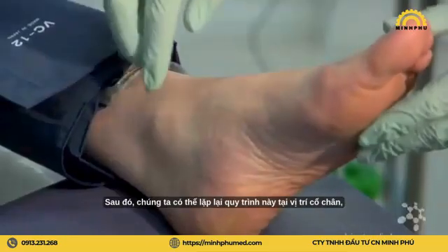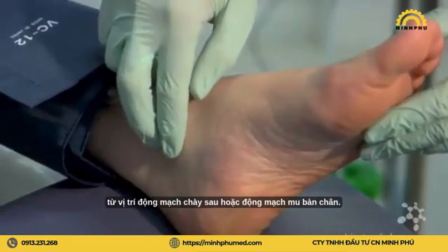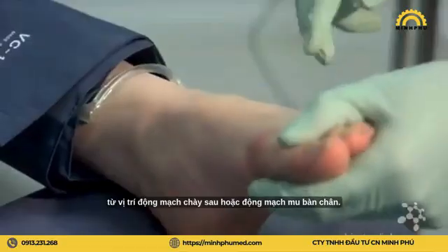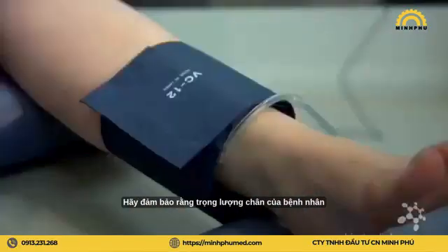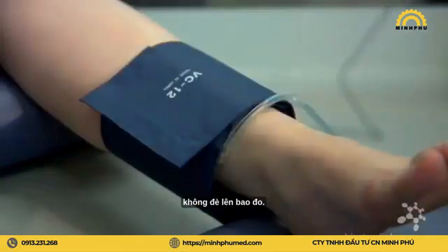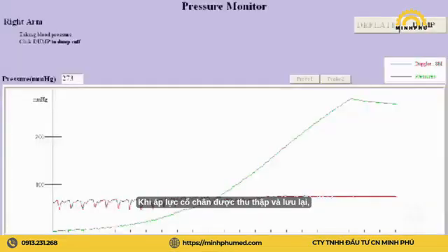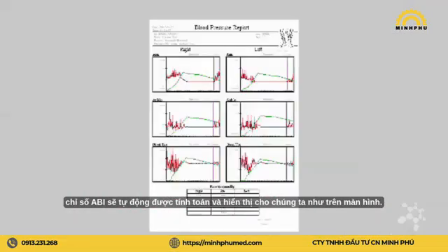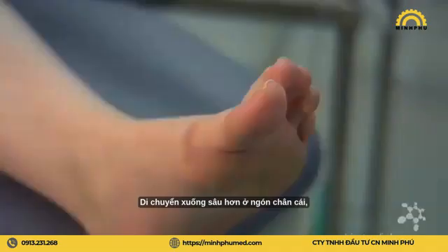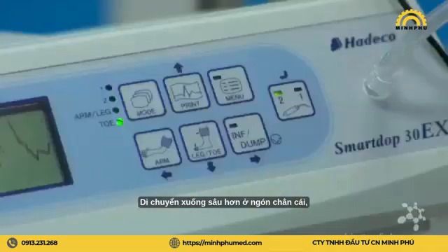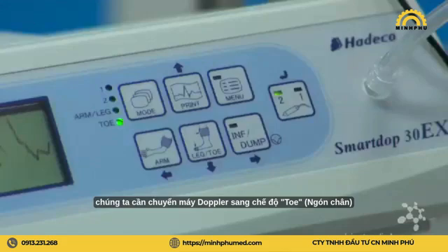We can then repeat this procedure at the ankle site from either the posterior tibial or the dorsalis pedis arterial sites. Ensure that the weight of the patient's leg is not on the cuff. Once an ankle pressure is obtained and stored, an ABI figure is automatically calculated and presented to us as shown. Moving further down to the hallux or great toe, we need to change the Doppler to toe mode and ensure that it's reading from probe position number 2.